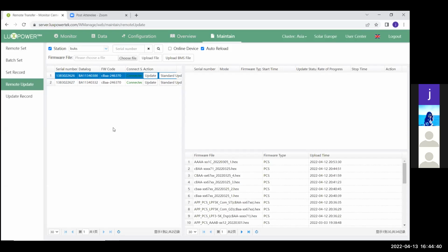So for this system, we can still do a new update. I see there is a new release at this moment. So if you press the standard update, it will show up here and the system will start to update. When your update is done, there are 3 updates on my inverters: my main board, my MPPT, and my communication board. That's why the 24 is for the MPPT, the 63 is my communication, and the 70 is my main board, if I'm not mistaken. But that's how my firmware code is developed there.